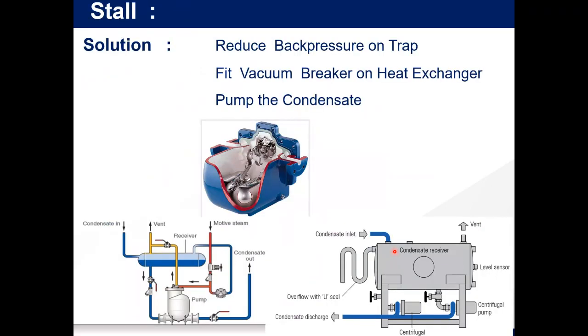So as it says here, reducing back pressure on the trap, you can fit vacuum breakers, as you were saying. So where you have the collapsing of steam after the control valve on a heat exchanger. I know I referenced the heat exchanger, but it's quite visual. Most of us understand how those work. If you put a vacuum breaker after the control valve on the heat exchanger, when the control valve closes, the vacuum breaker will then break the vacuum that's there and maintain a higher pressure on your inlet. And then the air will then clear. You need an air vent with that vacuum breaker to clear the air you've just introduced when the control valve starts to open.